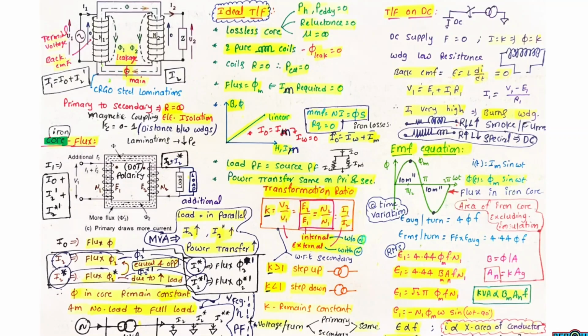Transformer core is mainly made up of iron, CRGO, silicon steel laminations. These laminations are approximately 0.6 mm. All these laminations are stacked together along with insulation in between them. This insulation can be paper, varnish, mica, or any other insulating material. These laminations are provided in order to minimize eddy current losses. So the transformer core is completely laminated along with insulation and stacked together.